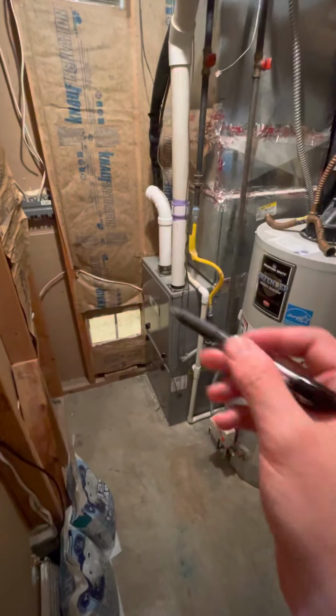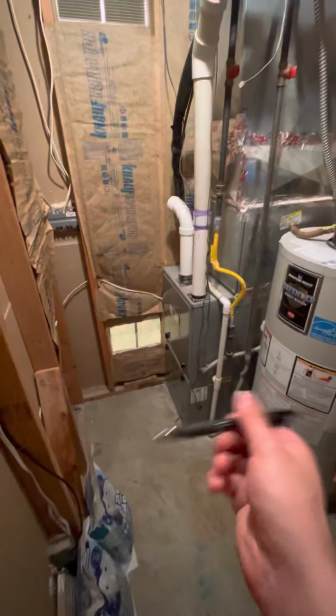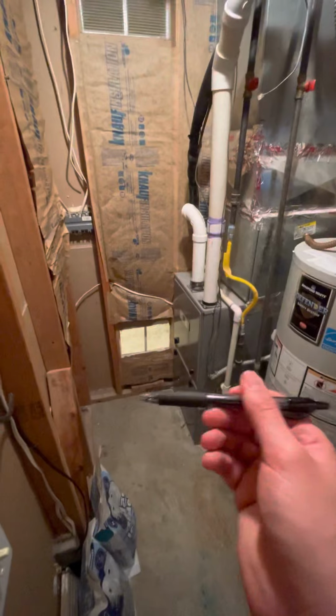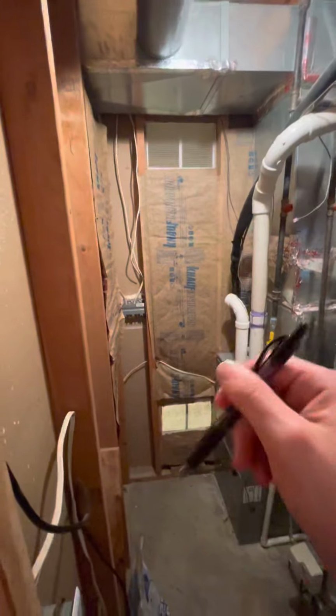I would like to keep this entire setup. Really no sense in changing that out, but we will get rid of that existing filter and we'll just leave it so it has that fresh air, that cold air return working. And then on here, this is actually where I'd want to build quite a bit of ductwork to connect all of that to the furnace coming in on this side, put the furnace on a base can and have one filter right underneath the existing furnace. And we'd be doing a 16 by 25 by 1 with a filter rack. And I'd probably do a pre-built system because you have 82 inches all the way up to where it actually starts to run for this entire setup. So that's the thought process there.